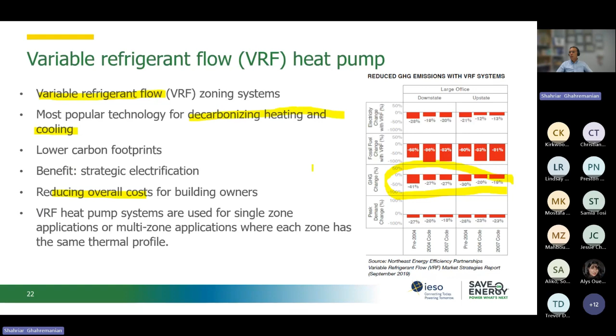And the multi-zone application means that they can actually heat up at the same time that they cool down actually. So I have one example in the next slide. But before that, there are many studies about variable refrigerant flow heat pumps, or VRF heat pumps, and they show a large amount of GHG emissions that you see, and also fossil fuel for sure. When we switch to variable refrigerant flow heat pumps, we are going to reduce the fossil fuel need by almost 60 to 80%, and also get around a 30 to 40% reduction in our GHG emissions depending on the existing system that we have actually.